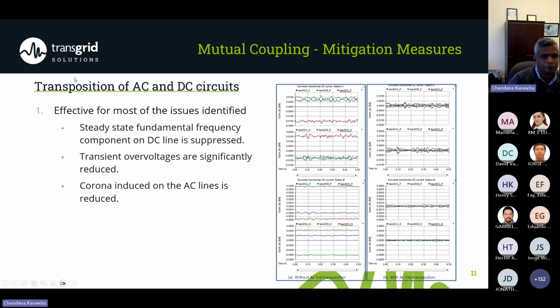But the thing is, transposition is not that easy. You need special towers to do this. But if you can do at least a few transpositions along the corridor in parallel, that will help to reduce the mutual coupling significantly. Here you can see some of the simulation results with and without transposition. And here, this is the DC current appearing on the converter transformer. You can see that we got rid of the DC current by having the transposition on the AC line.